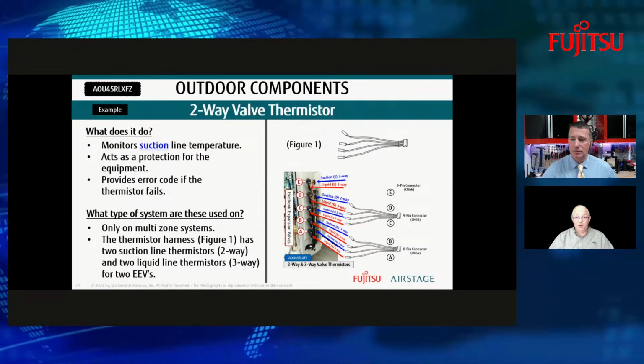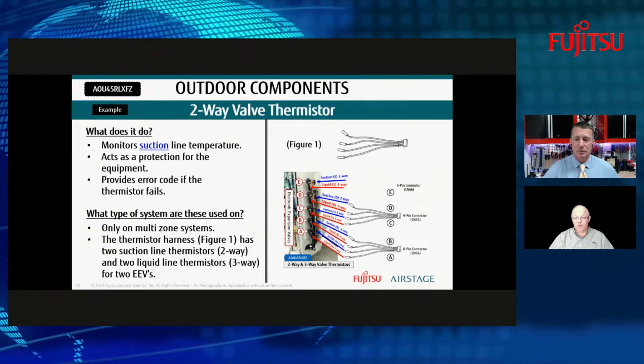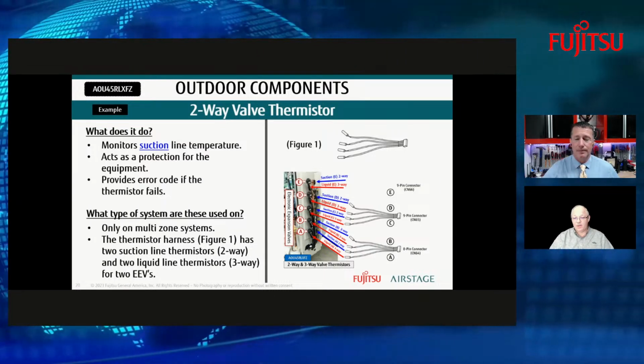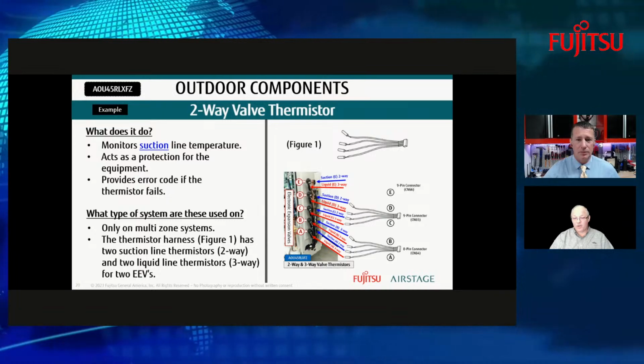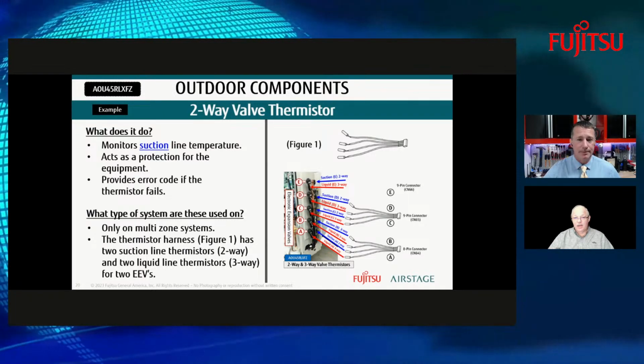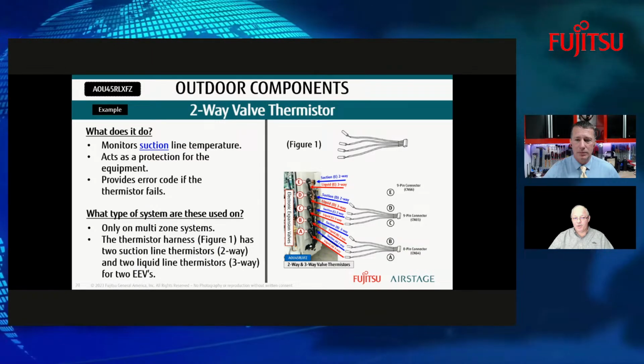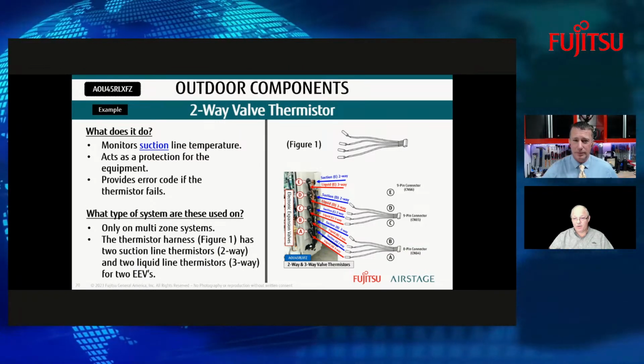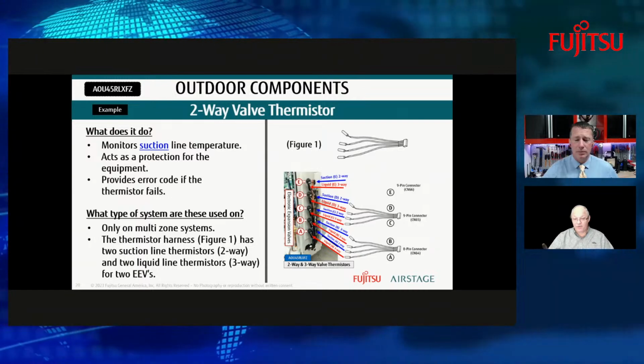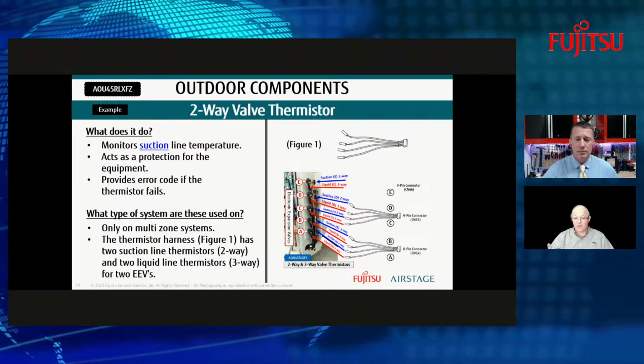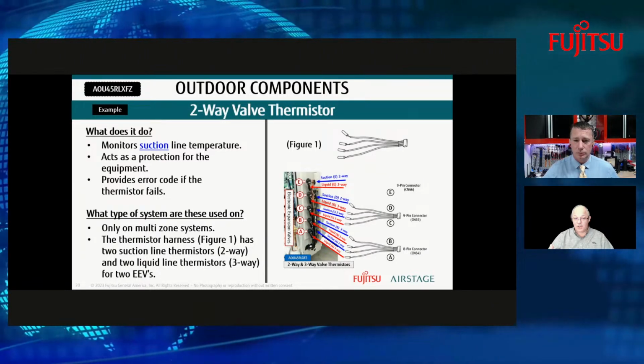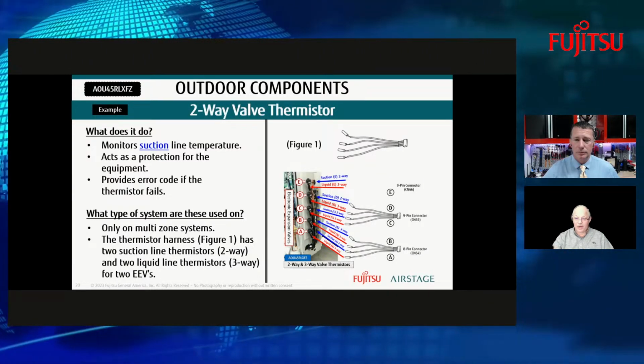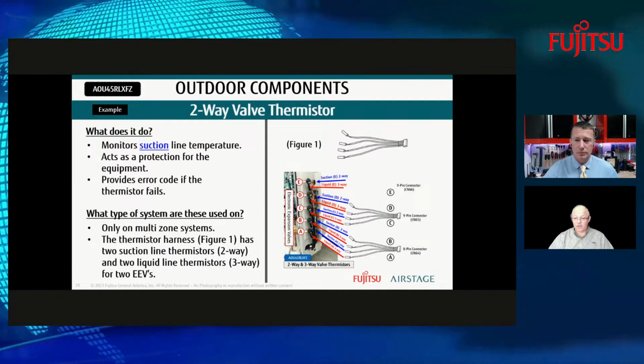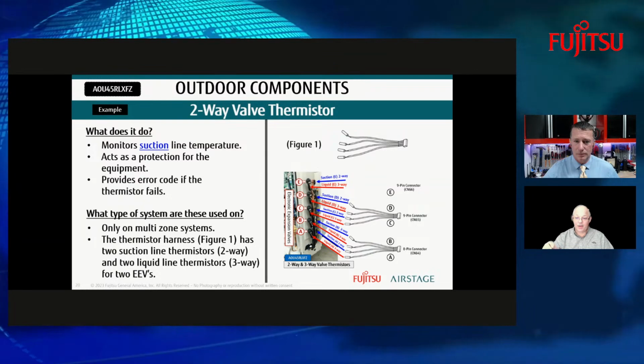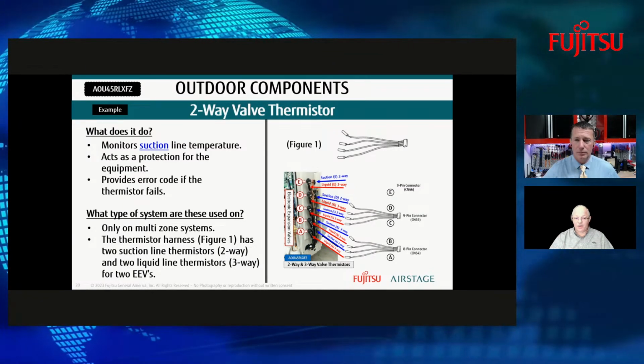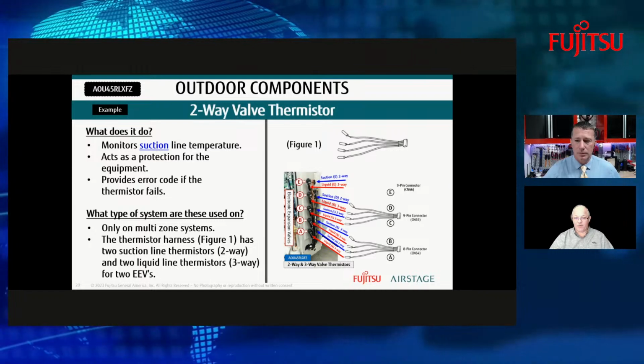Now, when we get into the two-way thermistor, this is in a multi-zone system. You can see we've got 5 different EEVs in the outdoor unit. So this is a 5-zone system. Multi-port. It's monitoring the suction line temperature, and again, it's acting as a protection as well. It can also provide an error code if it needed to. And you'll see these used only on multi-zone systems where you've got these 2 for each of the indoor units. So each indoor unit, A, B, C, D, and E, they have their own respective ones for both the suction line and for the liquid line.